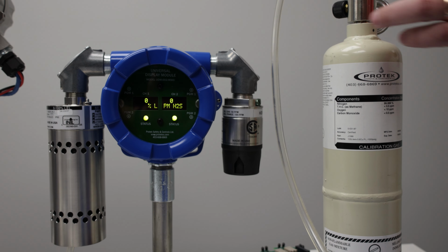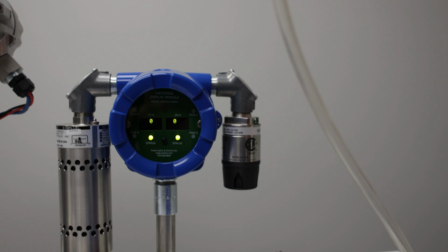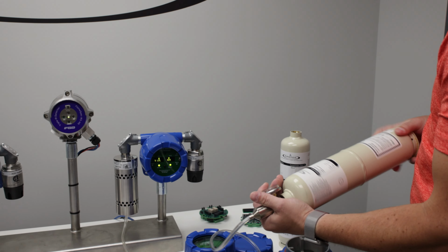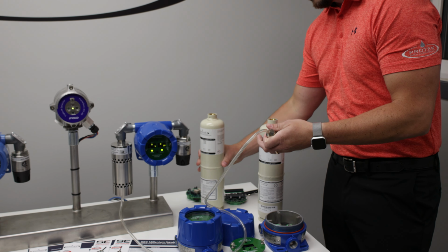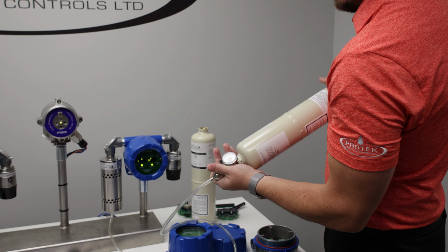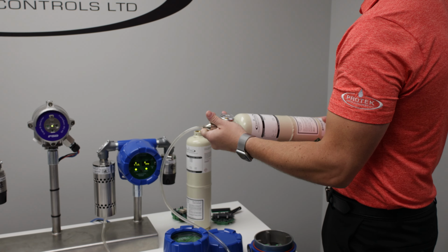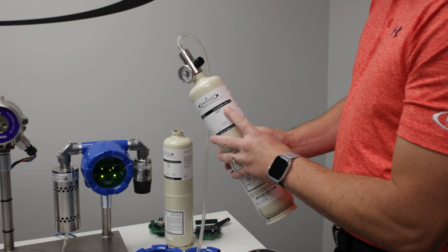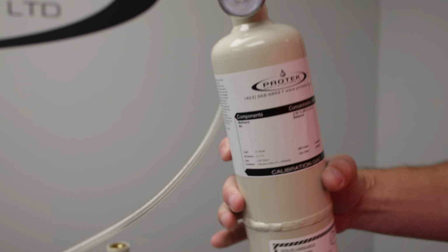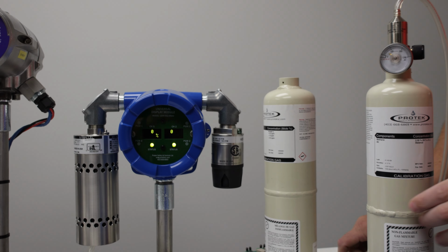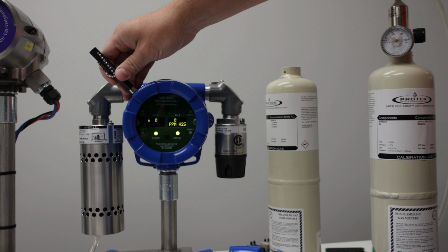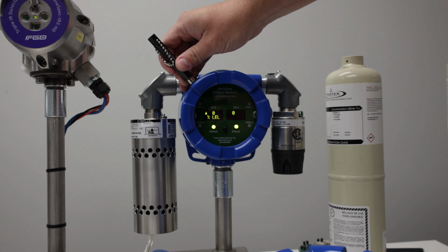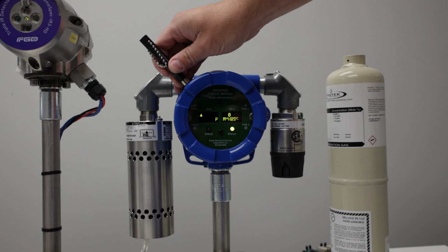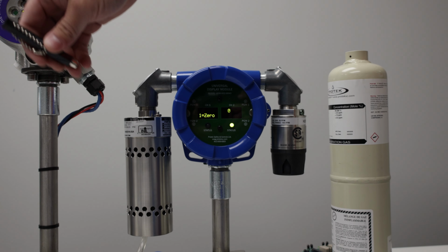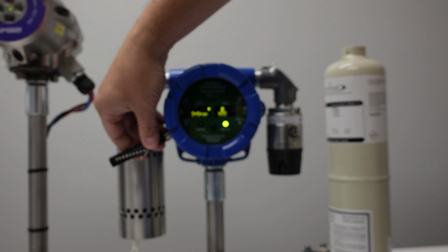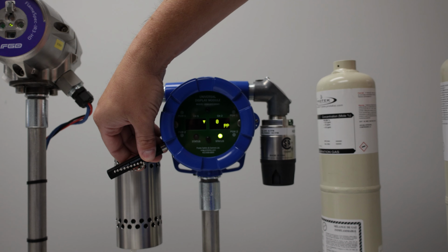Now what I'm going to do is switch up my gas. So I'm going to take off my regulator here and switch from my 0 cal to my methane. If you take a close look, we're using 50% LEL methane on this particular unit. Now we're going to walk you through a calibration of it. So we're going to hold that magnet again on program 1 till the arrow comes up and goes away on its own. We've entered cal mode. Program 1 is your 0, program 2 is your span. So let's hold it on program 2 till that arrow comes up and goes away on its own again.